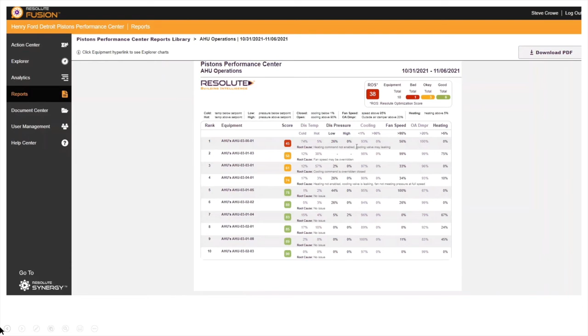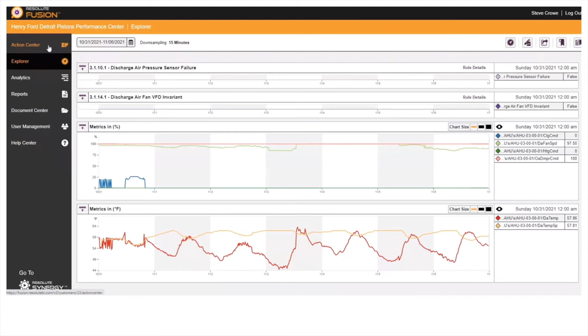Once we find the unit that's improperly working, we can look at the root cause, which might point to a leaking cooling valve. To investigate, I'd first verify this through the data as it populates, and once we validate that we have a cooling valve that's closed but still seeing a decrease in discharge air temperature across that coil, we can act on it.